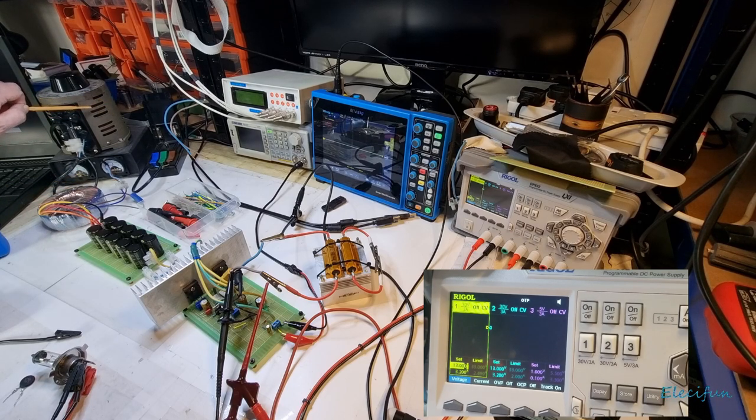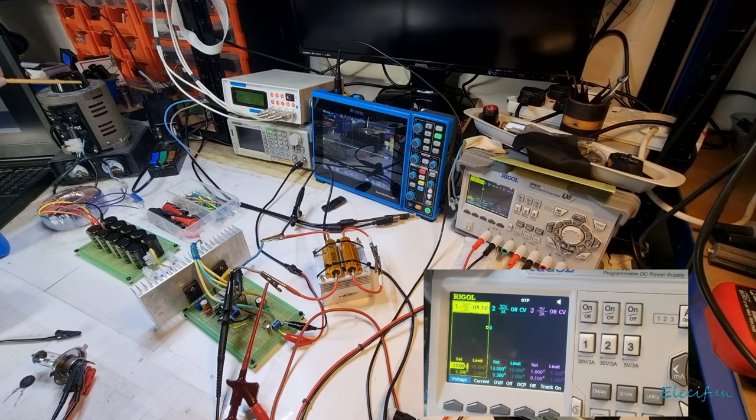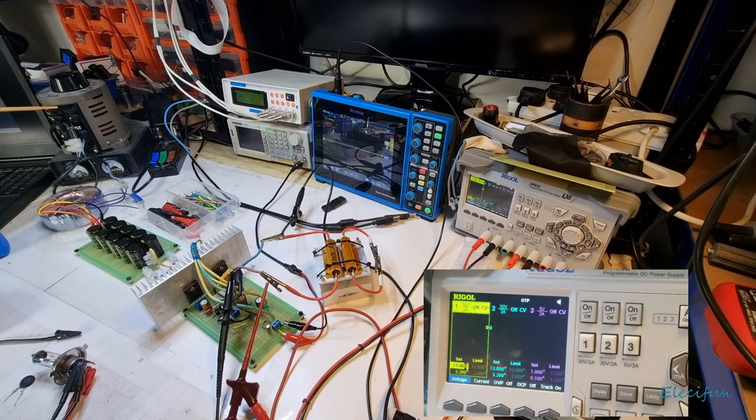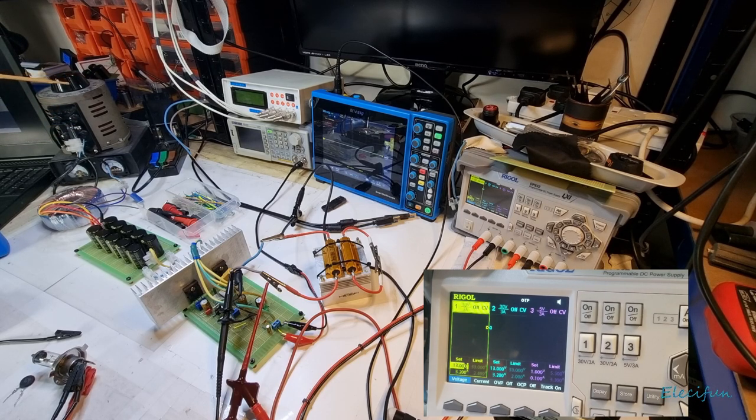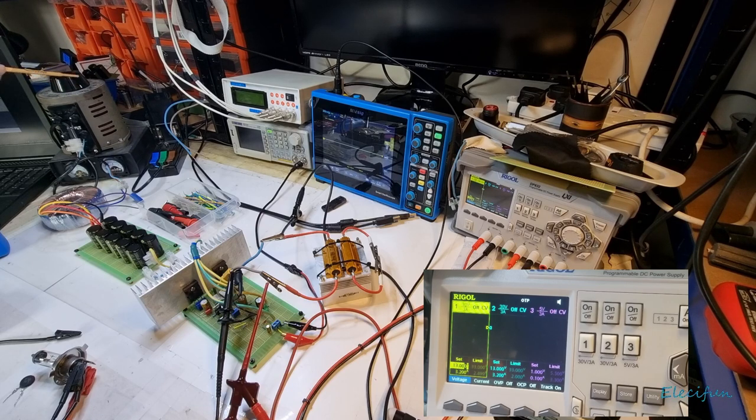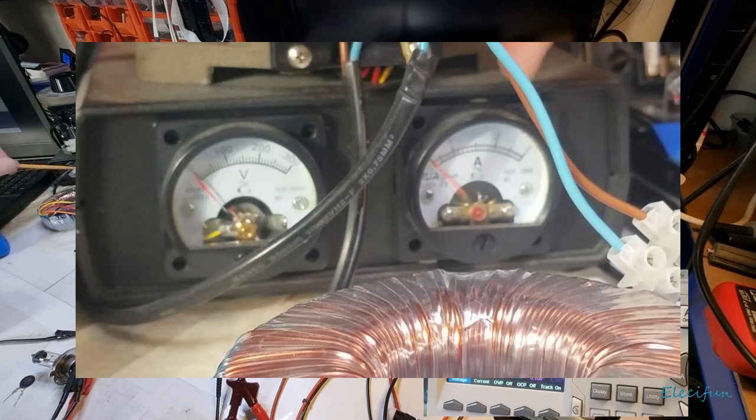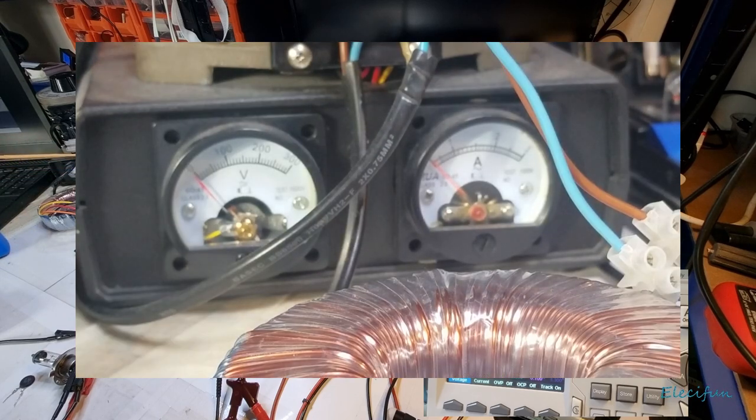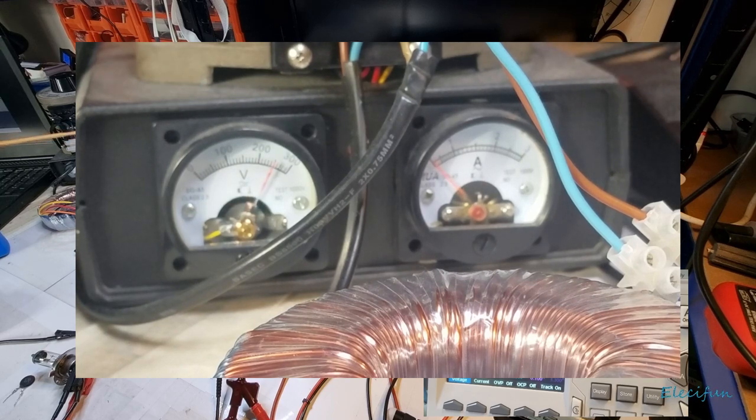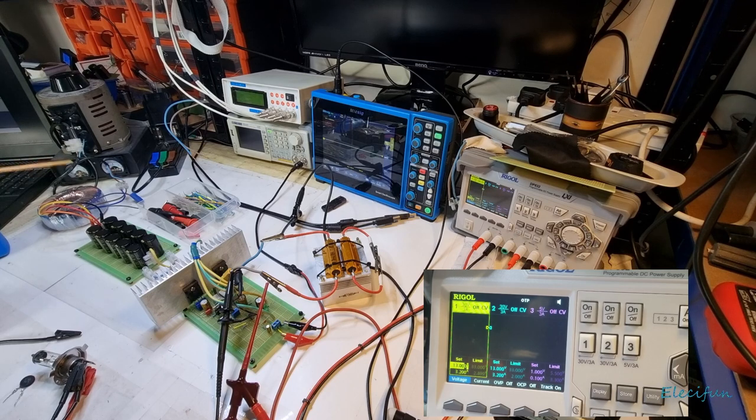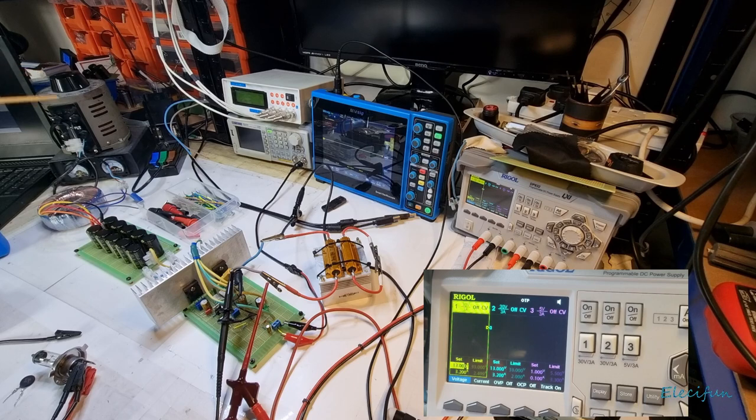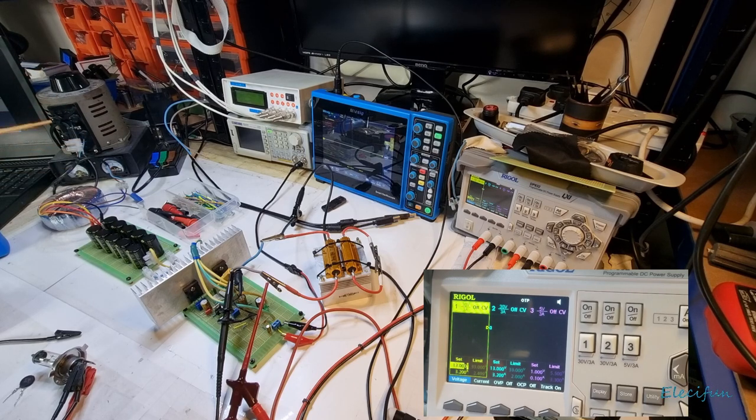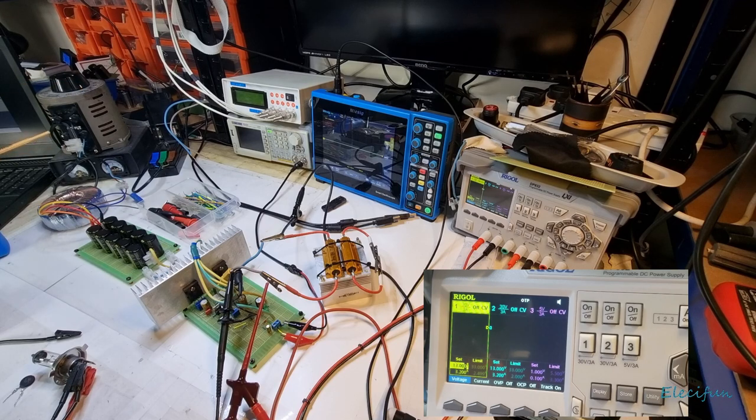And the same thing if you're using an auto transformer like this one here, it will have its own maximum current rating. On this one it's 2.5 amps. So if you just set this at 235 or whatever voltage and I just clamp that down, that needle is going to bounce across here and it's going to indicate that it's absorbed very quickly in a very small space of time, a lot more current than what it's rated for and that can damage it.